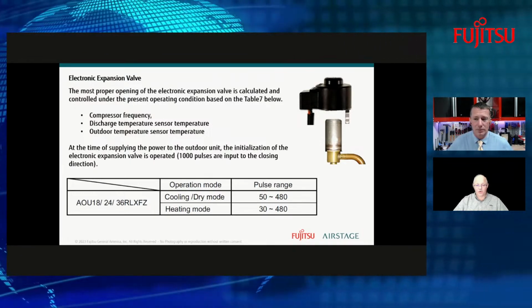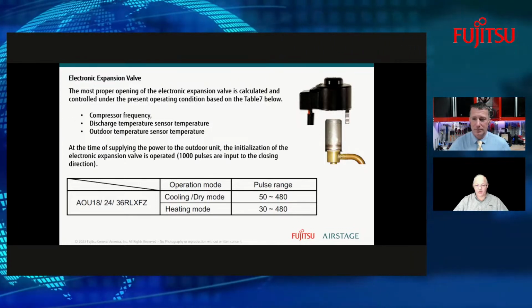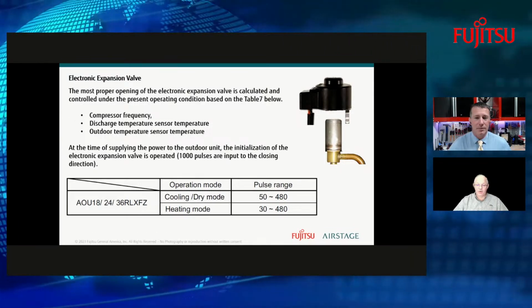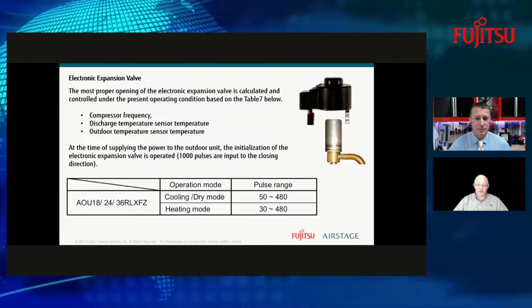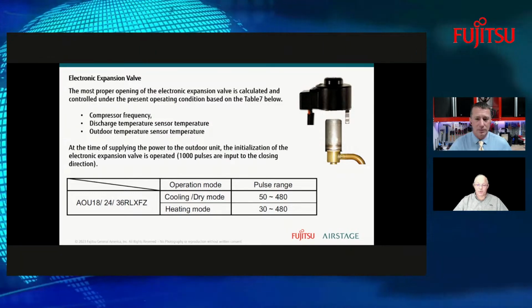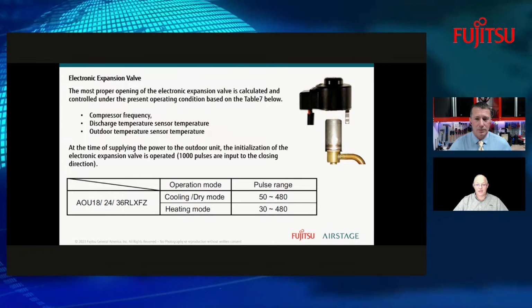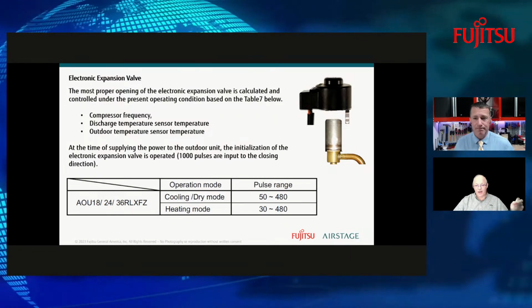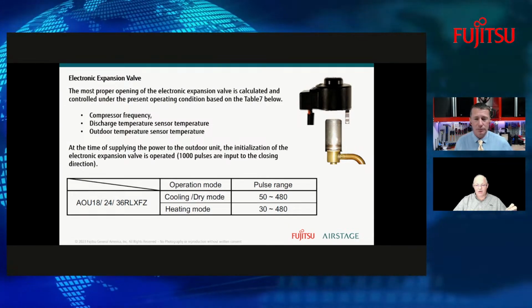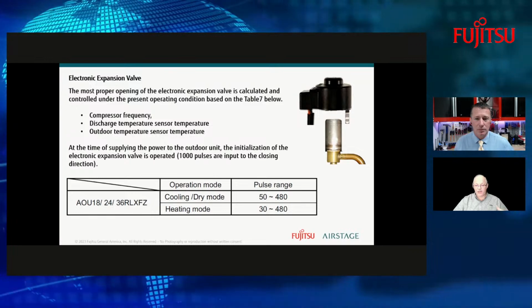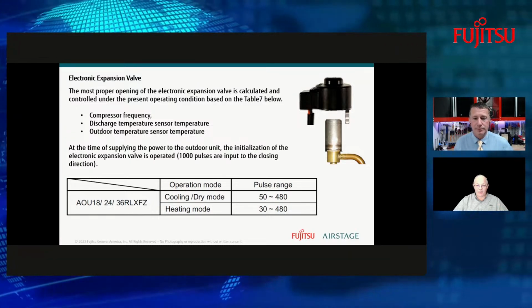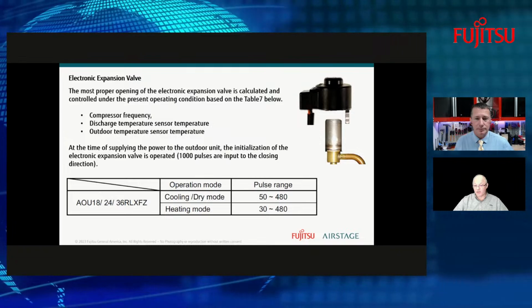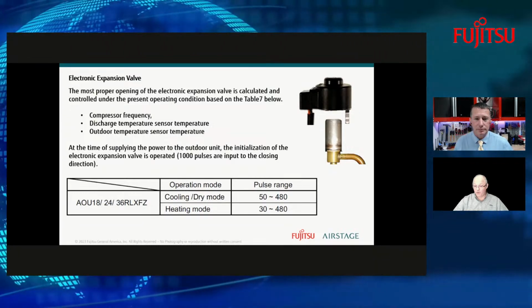So on an 18, 24 or 36 model of this particular unit, you can see that in cooling mode, we have a pulse range between 50 and 480. So it's going to pulse to at least 50 as the minimum that it could flow through. Now, that range is up to 480. Some other ones could have a little bit higher range, but in heating mode, you can see it's different than it would be for cooling mode.